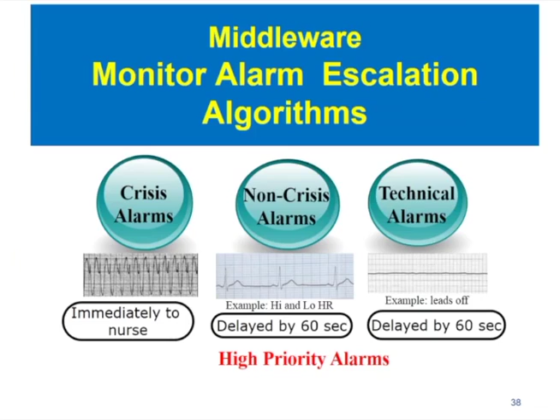The reason behind the 60-second delay for the non-crisis and technical alarms is to allow those alarms to auto-correct. We found that about 90% of alarms will self-correct, or they're being caused by staff who are already in the patient room and manipulating the patient, so there's no sense in sending them an alarm on their notification device. The delay minimizes the number of nuisance alarms being sent to staff, and that's why it's put in there. And as you can see, we err on the part of all crisis alarms being true, even though we know that they're not all true, and we do not put any delays on those crisis alarms.